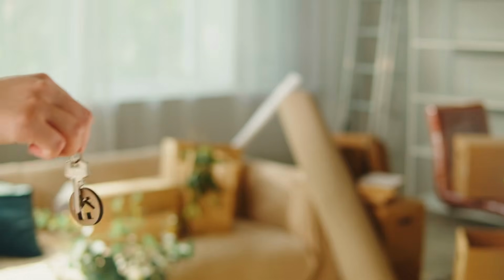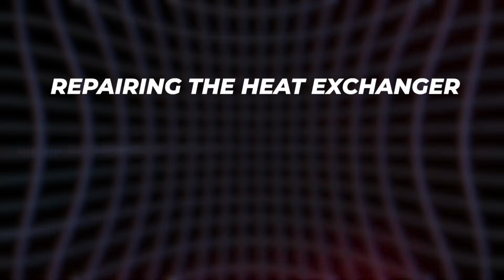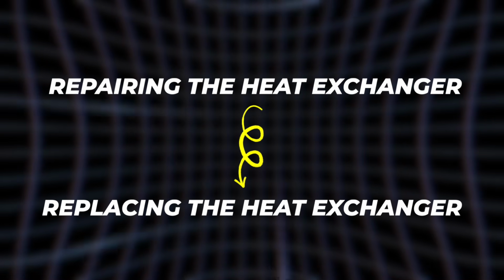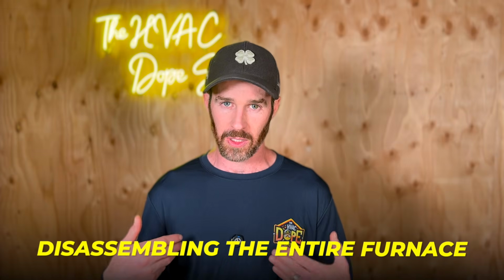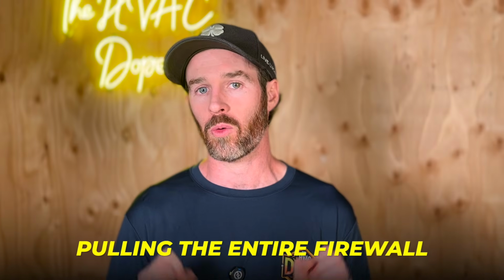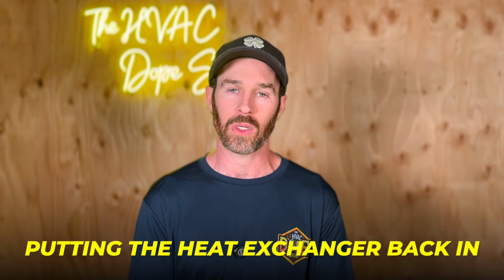So if you are looking to just do the absolute cheapest repair you possibly can to limp the system along a little bit longer, maybe you're selling the home in a few years, or maybe you're selling the home right now and you just found the crack in the heat exchanger and you want the cheapest possible repair just so it will pass inspection and you can sell it. Repairing the heat exchanger involves replacing the heat exchanger, and it's a costly repair because it basically involves disassembling the entire furnace, pulling the entire firewall, putting the heat exchanger back in, and then reassembling the furnace.